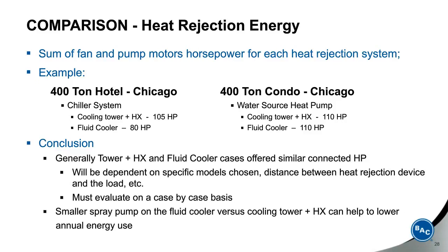Did the installation cost include the cost of commissioning? No, we did not look at the cost of commissioning in the study, but we tried to capture everything in the design, and that's why we asked IMEG to do the detailed design, so we could count up every fitting, every expansion tank, every strainer, every piece of piping and equipment in the system, so we would have a true installed cost. But that's a good point. We did not look at the cost of commissioning in this study.